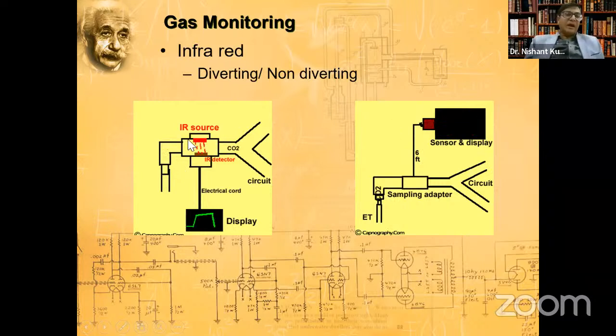What it does is, again, there's an infrared source. There's a cuvette. Everyone has seen a mainstream one. There's a cuvette with a removable piece, and there are two circles in the cuvette. There's an infrared source in the console, and air passes through the cuvette. Now again in the console, there's an infrared source, a measured wavelength is passed, and there's a detector here.